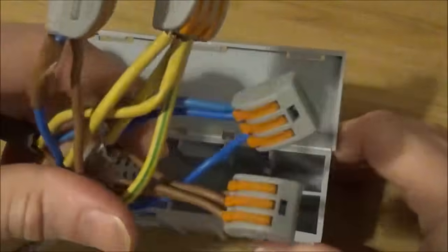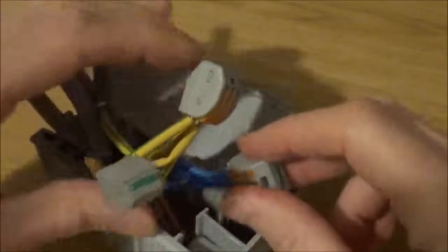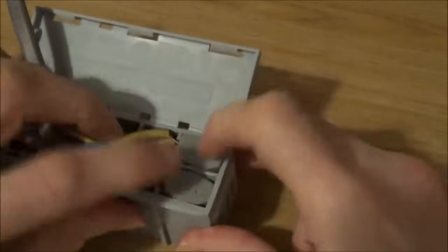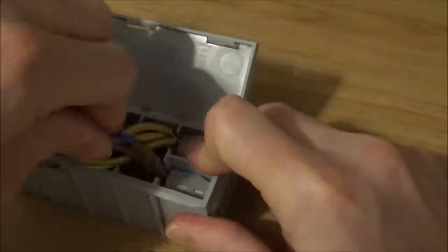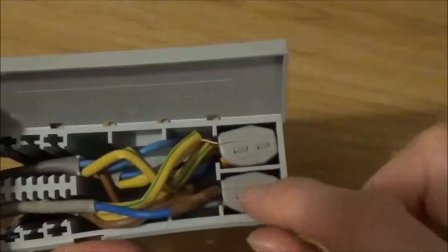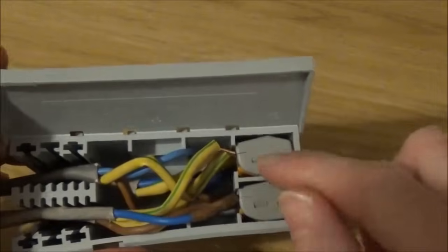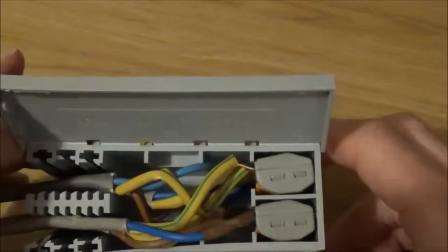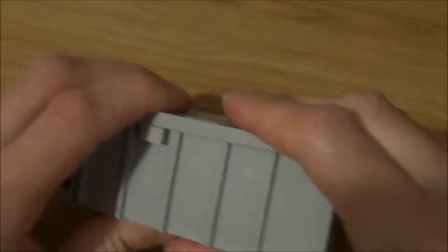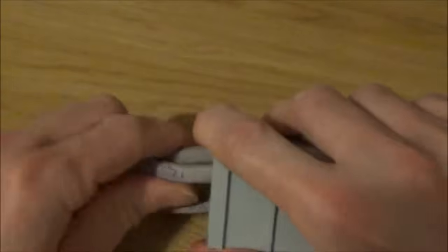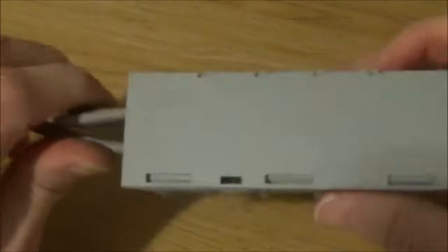For example with these, push them into the box like that. Those two go in there. Then you can push those two on top and your cables just squeeze between those fasteners. If you're just using the twin terminals you can fit three in each side. If you're using three or more you can only get two in each side. Just give that a good squeeze together. The Wago box is securely fastened and that can then push up into the ceiling and these cables are secure and can't pull loose from the connectors.